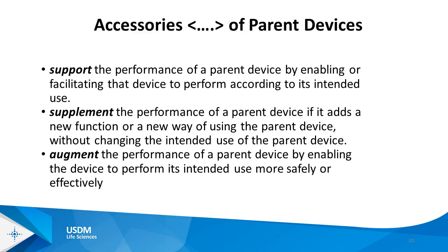You then have to determine how is that device on the market, what is its pre-market path. Is there a potential that it has an independent path, Class 1 exempt for example, or is it subsumed, which is kind of the default condition, under whatever the parent device's clearance or approval was? And that will then drive, of course, the timeline associated with that product. So if the accessory is part of a Class 2 510(k), then it's going to follow the timeline associated with that 510(k), and you need to line all that up both in terms of product code and whatever its path to market is.